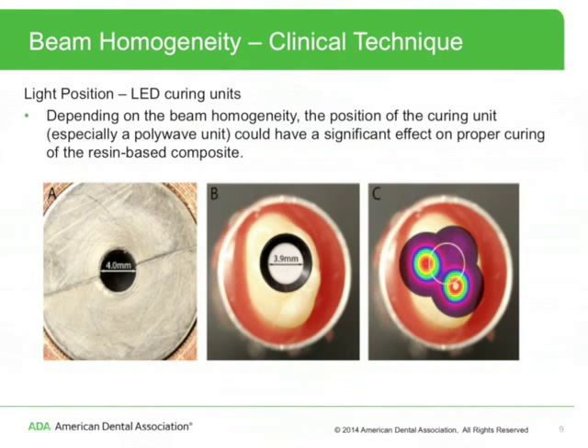Light position matters for LED curing units. Depending on the beam homogeneity, the position of the curing unit could have a significant effect on proper curing of the resin-based composite. Image A shows a depth of cure mold with its 4 mm inner diameter. Image B shows a 3.9 mm diameter irradiance probe used for radiant power measurements superimposed over a third molar. Image C shows the beam profile for one of the curing units superimposed over a third molar, with the white circle in the middle representing the irradiance probe.